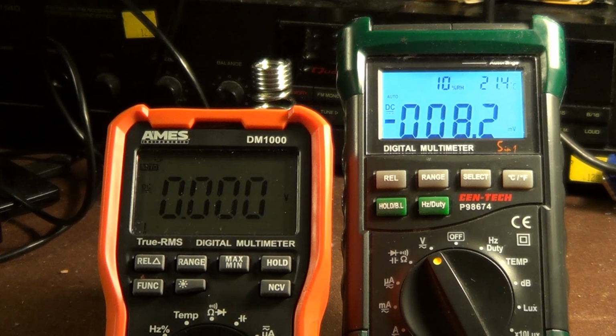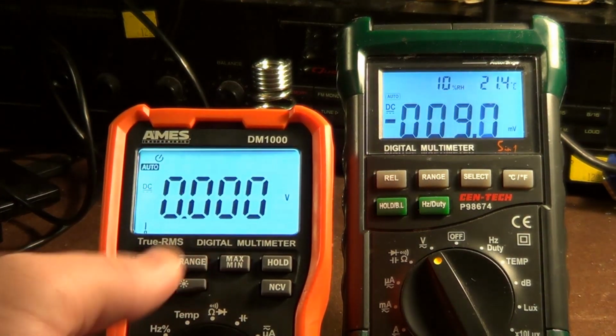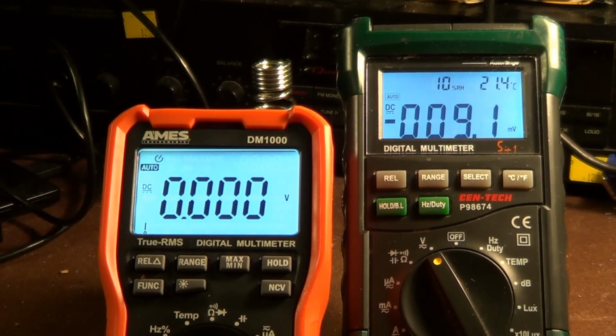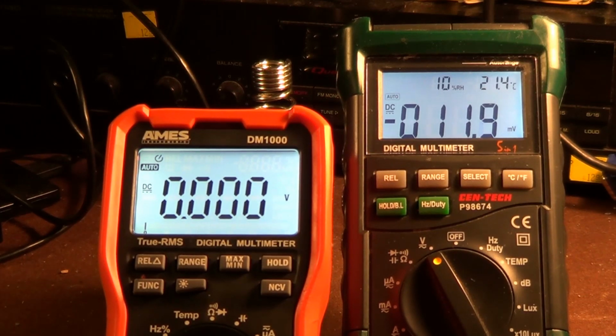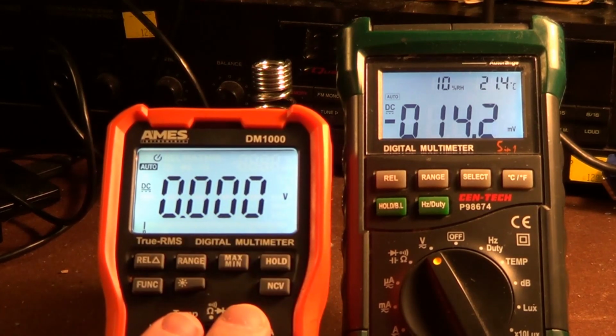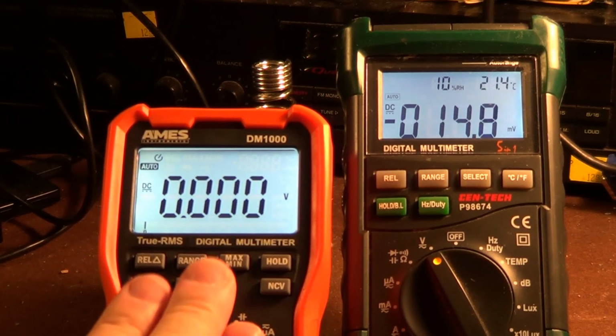I'll turn the backlight off just so you can see. The digits look good in the dark, but I have found in certain room lighting situations, such as when I had this up in the dining room earlier, where we're using LED light bulbs, that the unilluminated display was really quite difficult to read. And I don't know if it was simply a matter of the two driving frequencies, the ones from the LED lamps, as well as the display multiplexing that's done by the microcontroller inside this meter, if the two were simply beating against one another in an awkward way, making the display even harder to read, but it's certainly worth considering. And in this one, the display backlight only remains on for 1 minute, so I think that definitely counts against it.